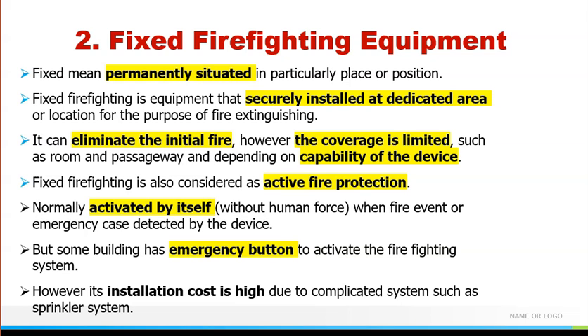Okay, so it is also used to eliminate the initial fire. However, the coverage is limited. Sometimes not the whole building is covered, maybe just the pathway or near the exit. And fixed firefighting is also considered active fire protection. Usually it activates by itself, in which they have a sensor. They have a system to activate the equipment.